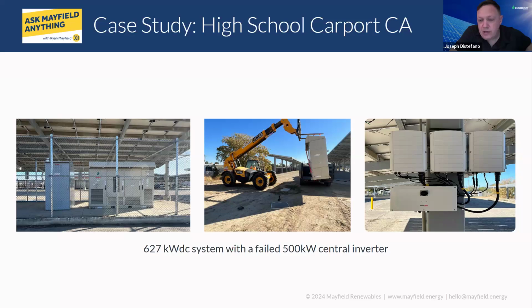Great thing about this project was it was in a parking lot of a school, and they did not want us to saw cut the parking lot. Ryan's team did a great job with due diligence, going through the conduit schedules, checking existing conductors, vetting new conductors, and working out pipe fill. It was a pretty interesting project. We removed the 500 kW unit and installed SolarEdge units at each carport with optimizers. We selected the SolarEdge product because we had a 208 volt AC output, limited by some car chargers already on site. At the time, before SMA came out with their new line of inverters, there was no other solution. I believe, Ryan, this was a 208 inverter we installed.